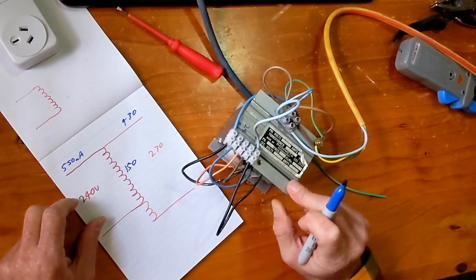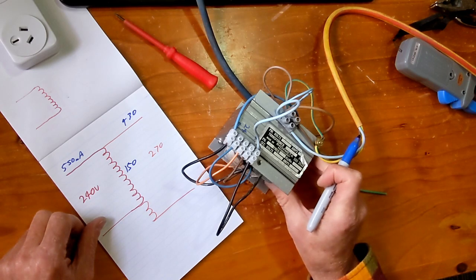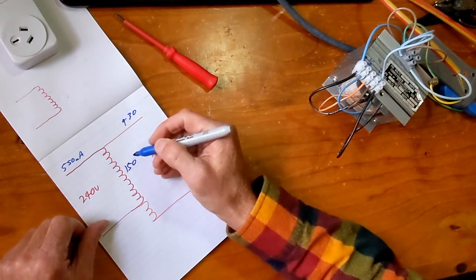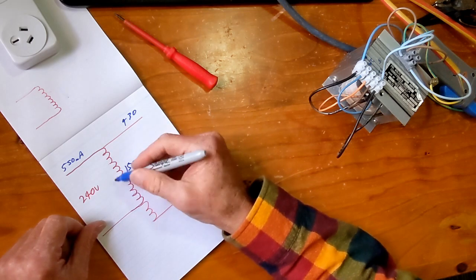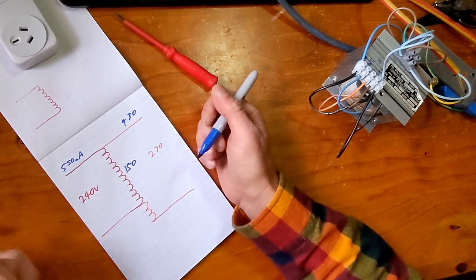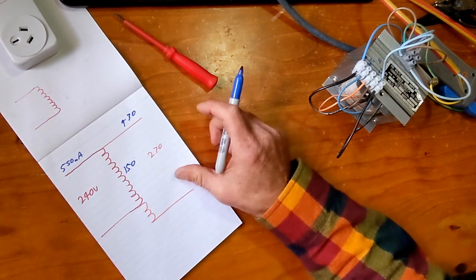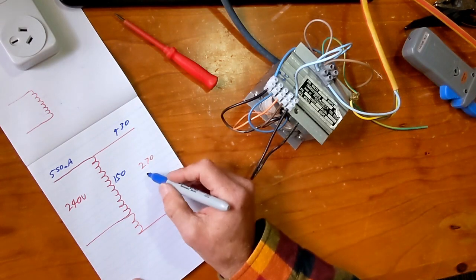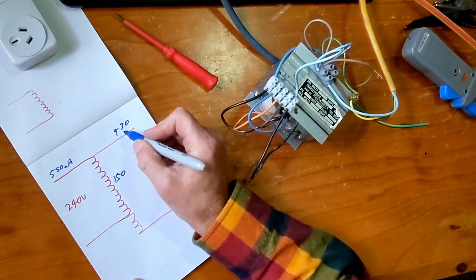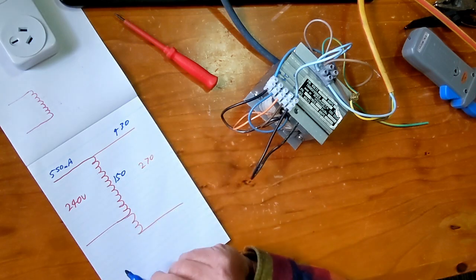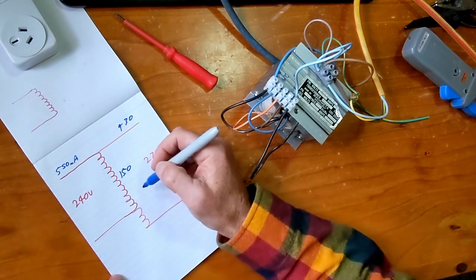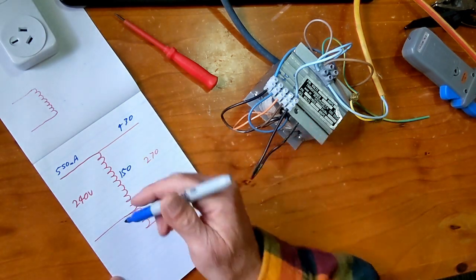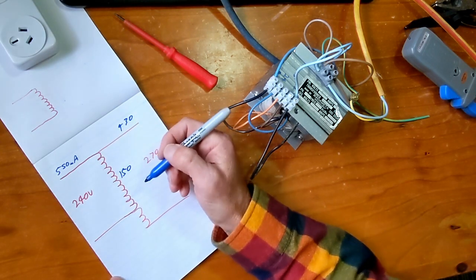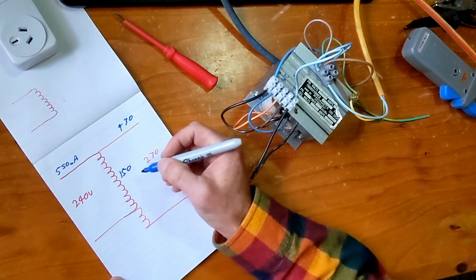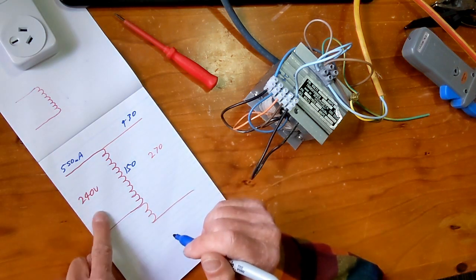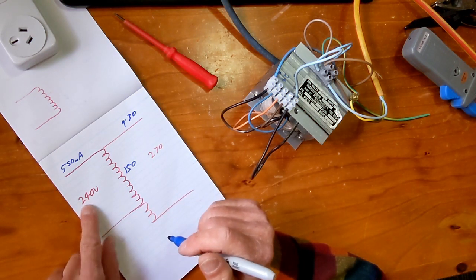This is a 100 VA transformer, and the primary can take 0.3 amps, so we're only using half of the current that's available to that. So what we've managed to achieve is by increasing the voltage on the secondary side, the current was reduced. Magic! In the centre of the transformer, the primary winding, the one that had the smaller cross-sectional area, we were down to 150 milliamps. Let's do some quick numbers for this side.